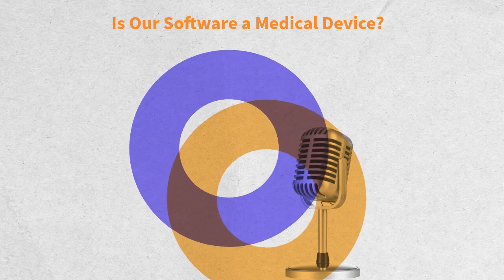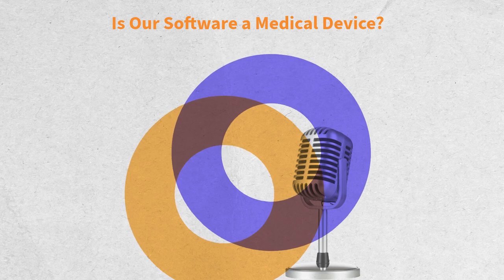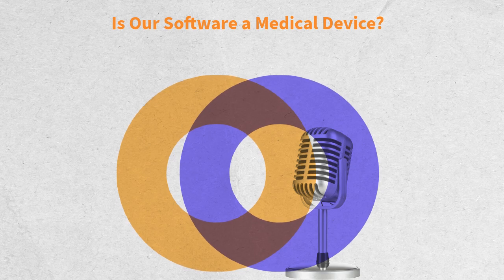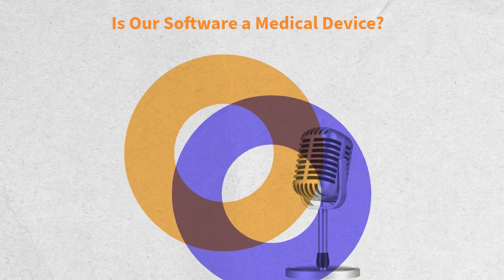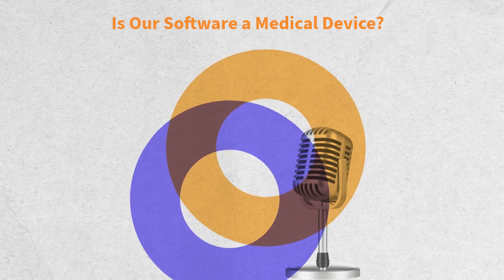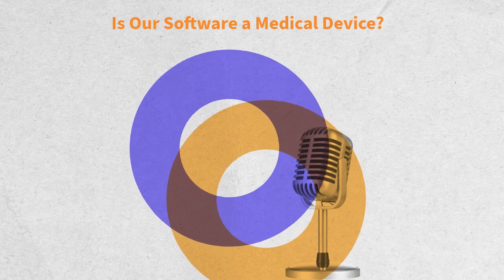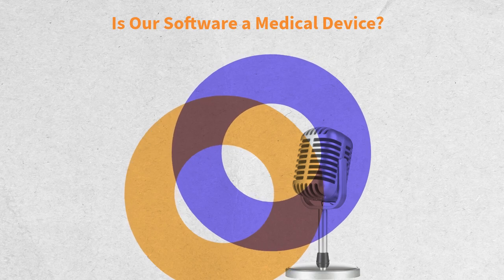What is the difference between medical software and wellness software? It is a subtle but crucial distinction. A wellness software only aims at improving one's lifestyle. Just think of those counting calories, tracking steps, or suggesting breathing exercises. A medical software, on the other hand, has a diagnostic or therapeutic purpose. This separating line is essential to establish whether your design falls into the field of application of the MDR.